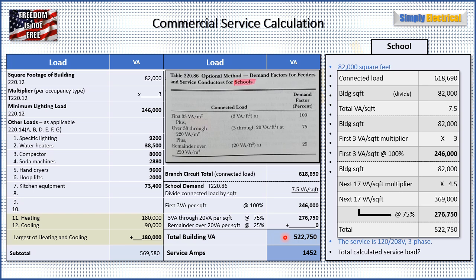We divide by our voltage — this is three-phase, so we multiply 208 volts times the square root of 3, then divide that into 522,750 VA. We get 1,452 amps, and that is our service size.